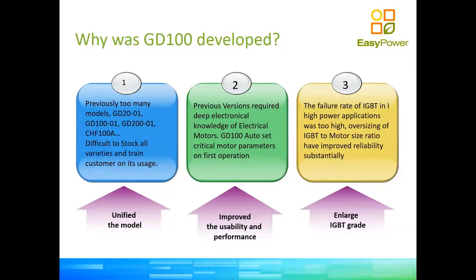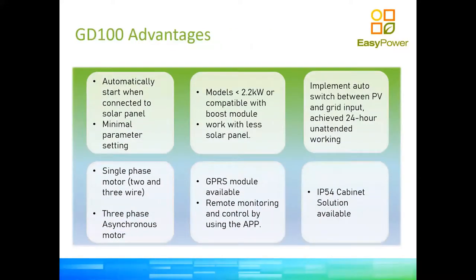The failure rate of an electronic component is proportional to the temperature at which it runs, which is proportional to current. With additional IGBTs, the current per device is reduced, keeping them cooler so the unit can operate in an enclosed device without excellent refrigeration. This gives the inverter a very wide and good operating temperature range, hence a much bigger warranty. That is the reason the GD100 was preferred over previous model generations of pump inverters.